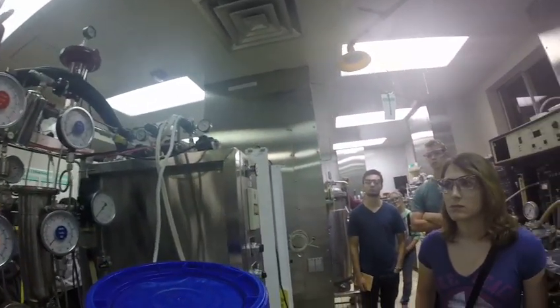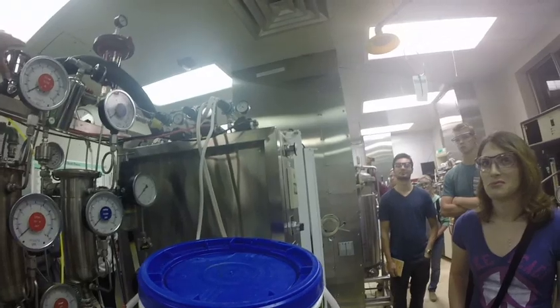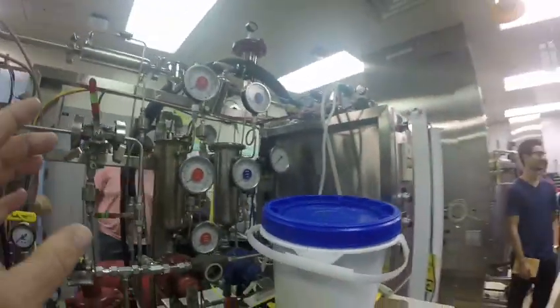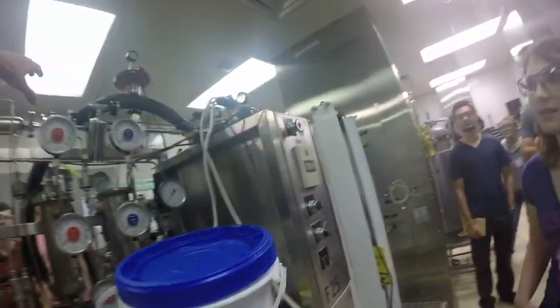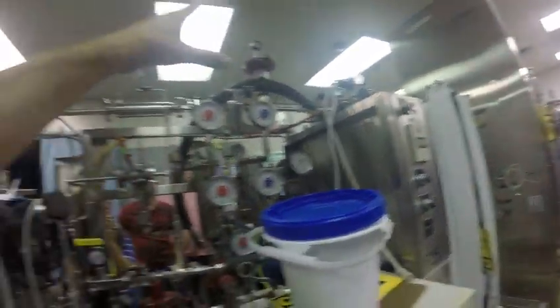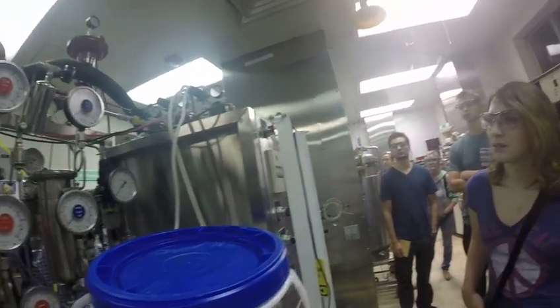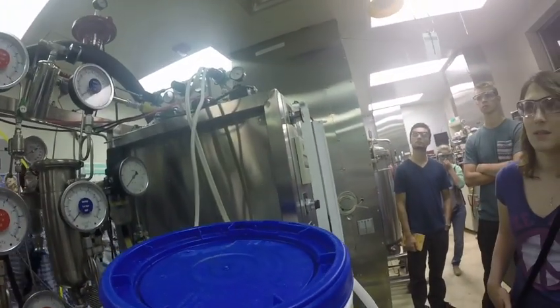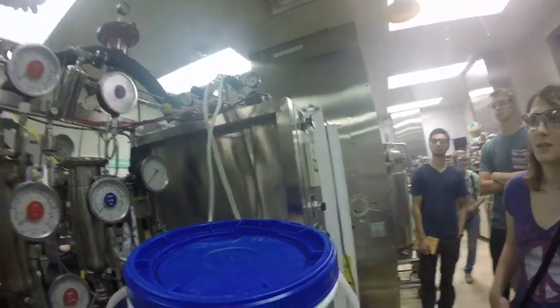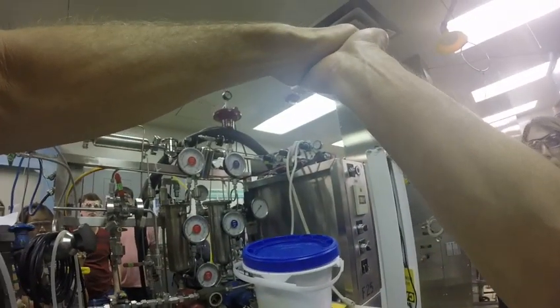And so what happens then is as you're steam sterilizing, for instance, this filter, okay, we haven't run this one in a while. If I was to take that and allow the steam to go onto this unit, it will clamp down on the steam, and then at that point it'll come to the source pressure of steam in the unit.